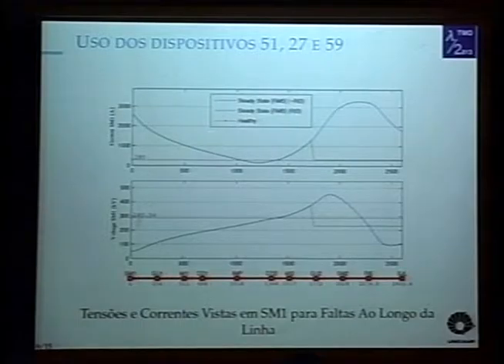In the current, this is also what happens. In blue, you have the behavior without the reduced insulation distance, in green the behavior with the reduced insulation distance, and in pink without fault. So for faults happening in the beginning of the line, the current rises a lot in comparison with the current without fault. As we move away from the sending substation, current drops. But it continues to drop until it becomes smaller than the current without fault. So here, when a fault happens, the current found in Serra da Mesa 1 is smaller than the current without fault. This is a specific characteristic for this type of line.